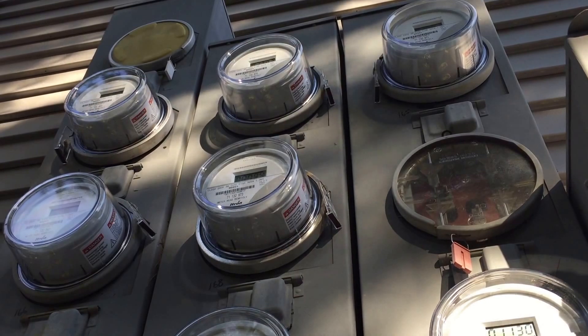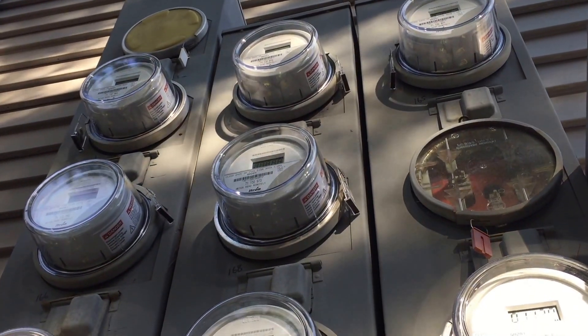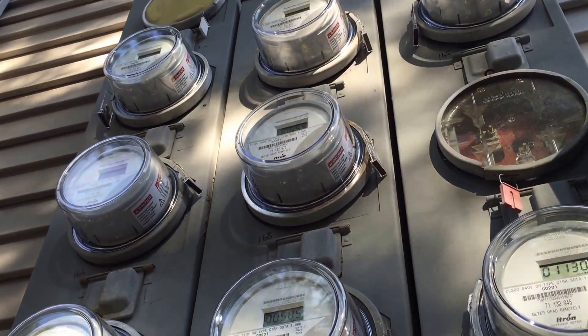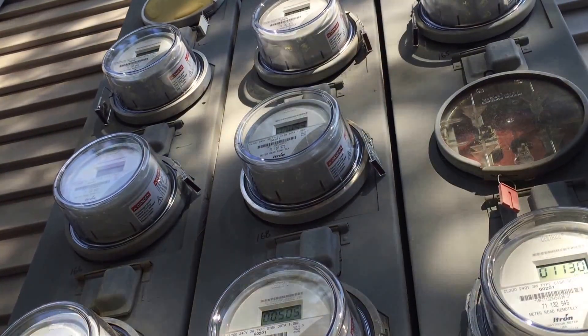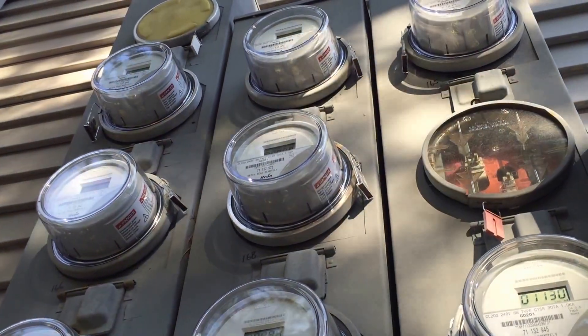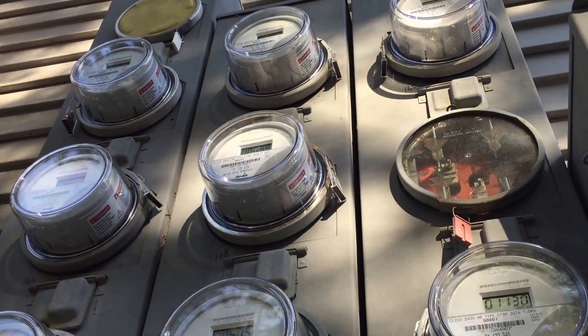These are well above that, so they are not readily accessible. It's going to make it really difficult to reach those — if I needed to shut one off in an emergency, I wouldn't be able to. I might have to find a ladder or some other means to reach it. This is Russell Blank, NEC consultant for EC&M magazine.